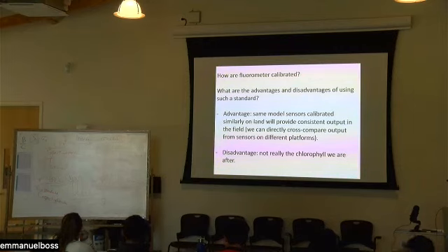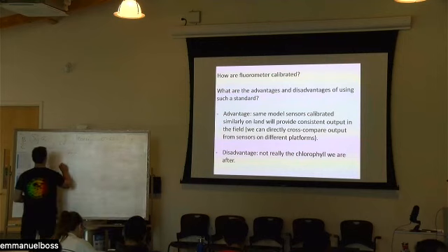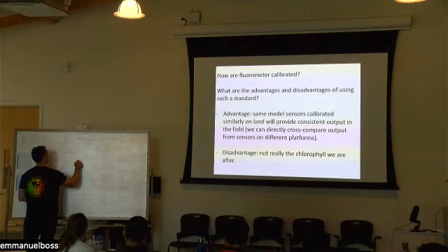Yeah, so how you calibrate is how you have to use it, right? When I calibrated, I had a certain protocol that I used. I've established the range over which it's linear, and I have an uncertainty associated with that. And then you guys come in and you use it, and everybody in this room used it differently.